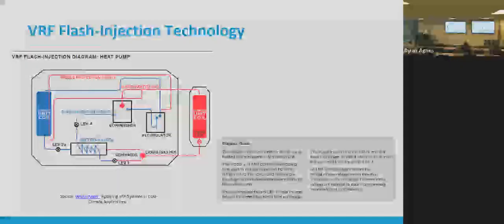Mentioned flash injection. This is a cool engineering thing. Does anybody know what causes an inverter-driven heat pump to have a minimum temperature outside? What's the problem? The engineering design challenge? Anybody know? Exactly. It's a heating problem. You're getting too hot. It's like you run a marathon, why can't you keep running? It's overheating because you're working so hard.